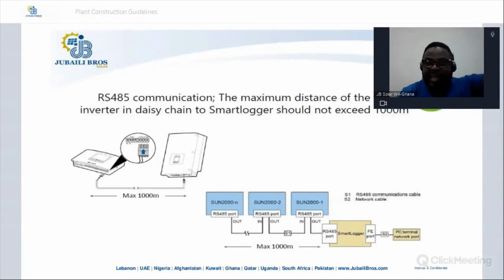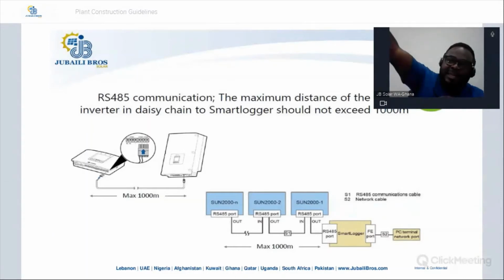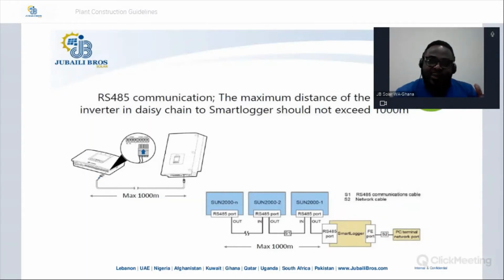But normally, if the inverters are interspaced in the field, all we are asking for, for the sake of communication, is this: if you are using an RS485 communication line for your daisy chain system, the distance between the furthermost inverter in the system to the smart logger should not be more than 1 kilometer. Remember, 1 kilometer is quite long. Okay, 1 kilometer, that's 1,000 meters, very long. So always just ensure that the distance between the last inverter in the chain and the smart logger location should not be more than 1,000 meters.